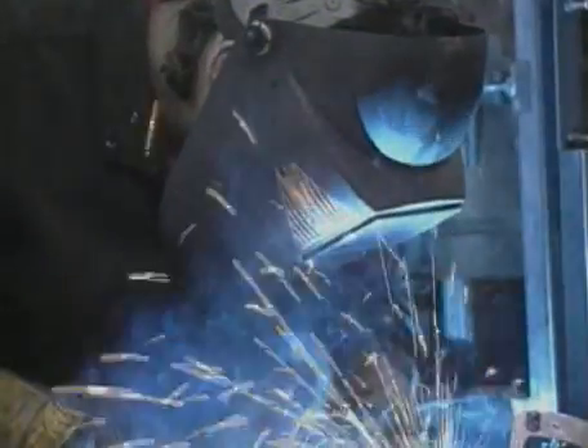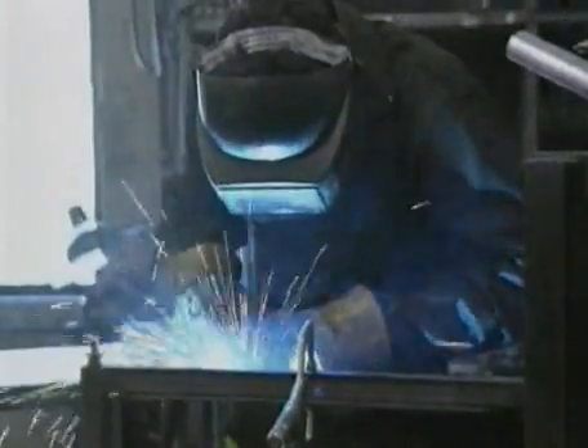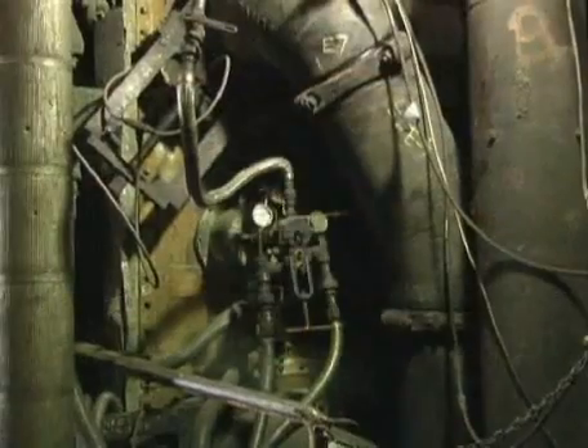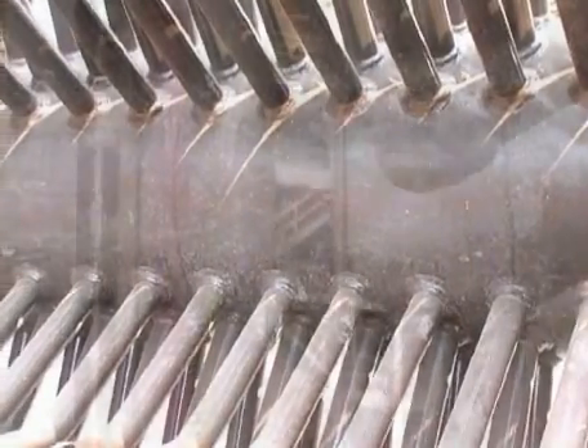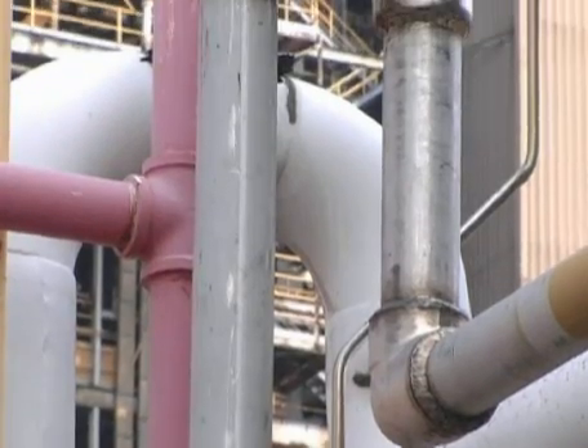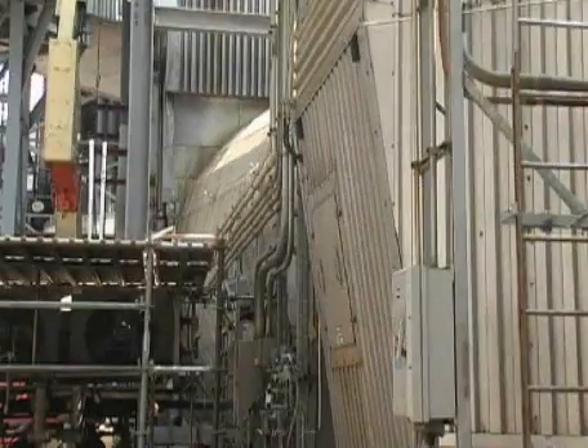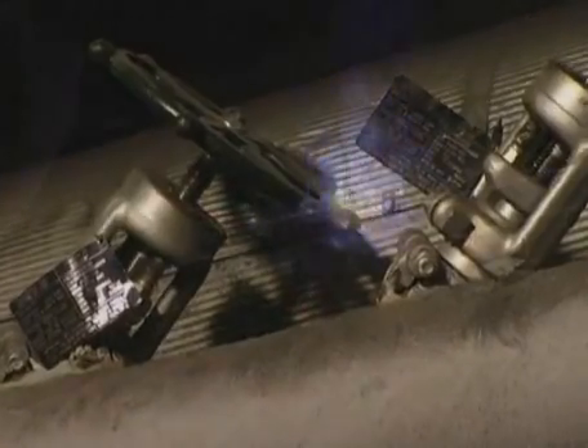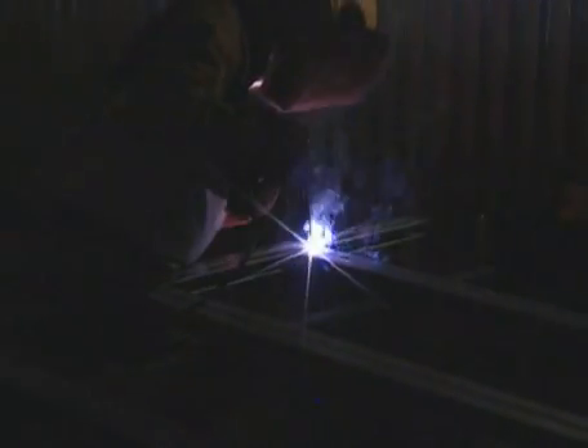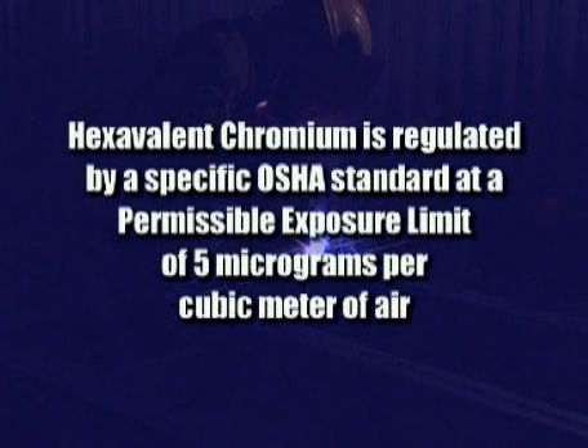You should also be aware that chromium is present in stainless and other alloy steels used in high-temperature boiler components, including boiler tubes, burner boxes, and header pipes, as well as in other metal components such as various types of piping and tubing, fan ductwork, and valves. Performing hot work activities such as welding, burning, and torch cutting on any of these components or equipment may generate fumes that contain airborne hexavalent chromium. Hexavalent chromium is regulated by a specific OSHA standard at a permissible exposure limit of 5 micrograms per cubic meter of air.